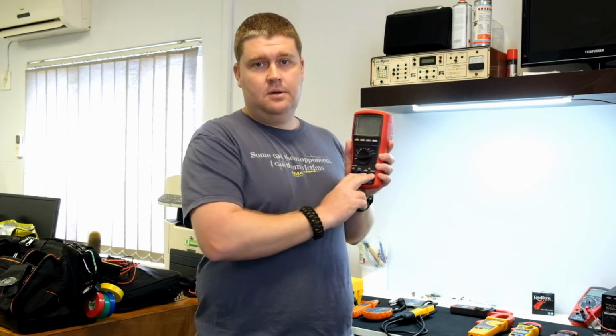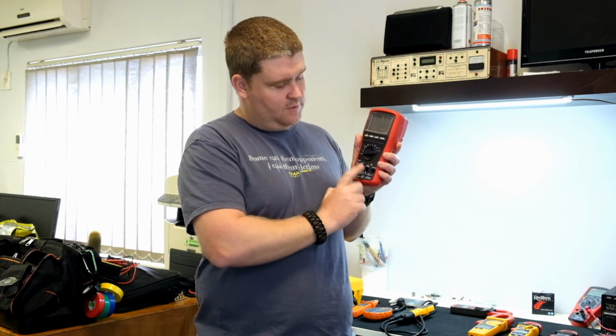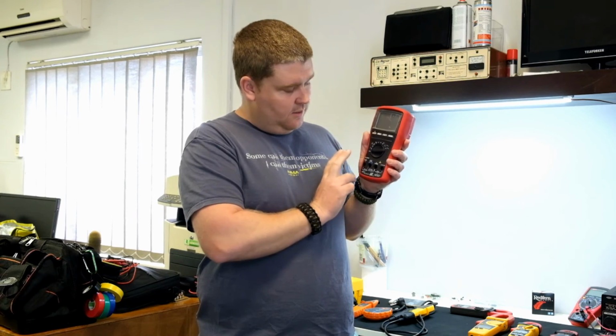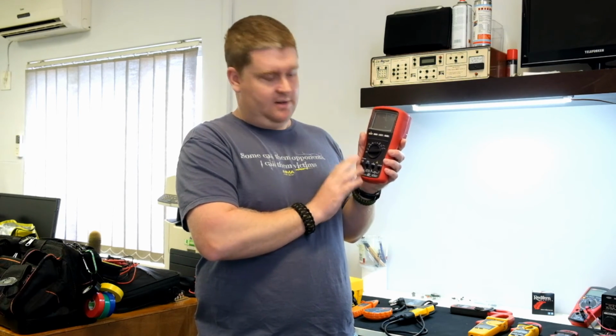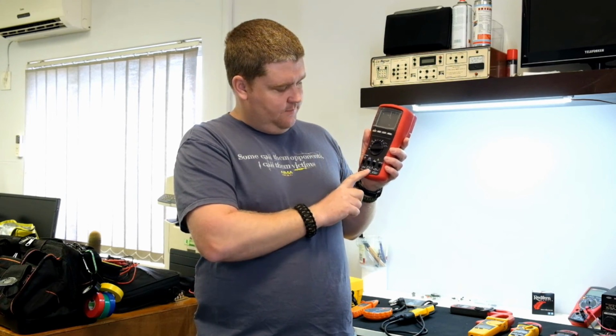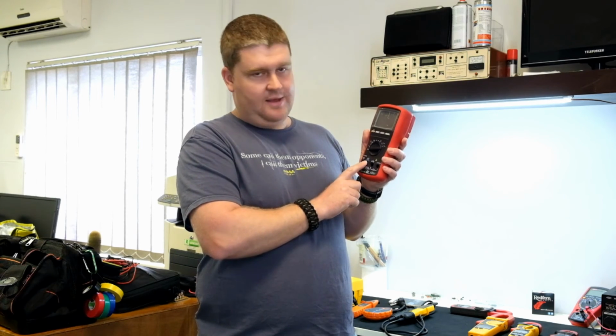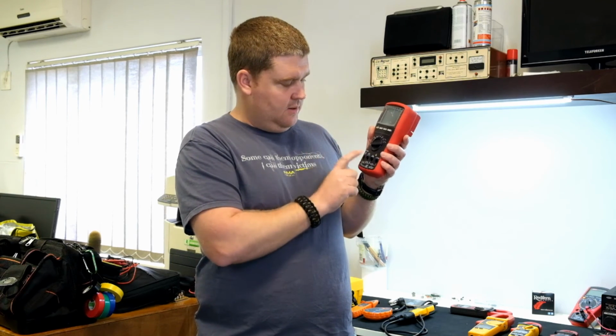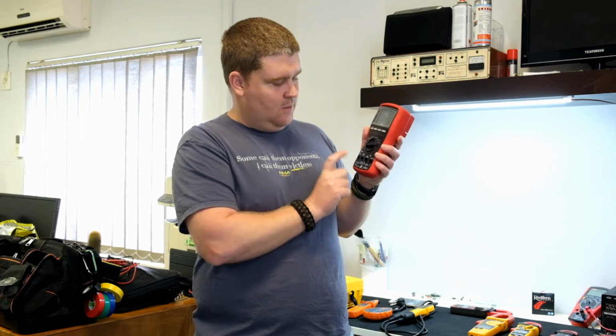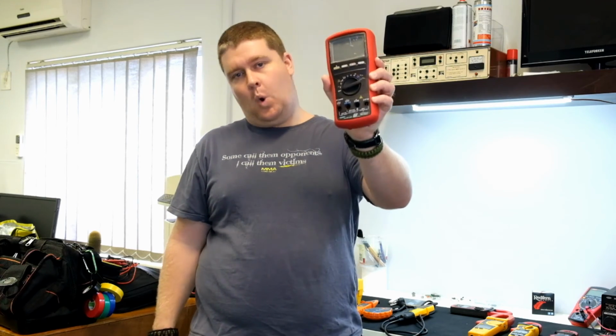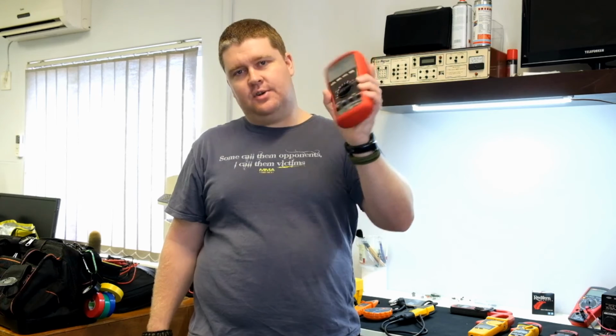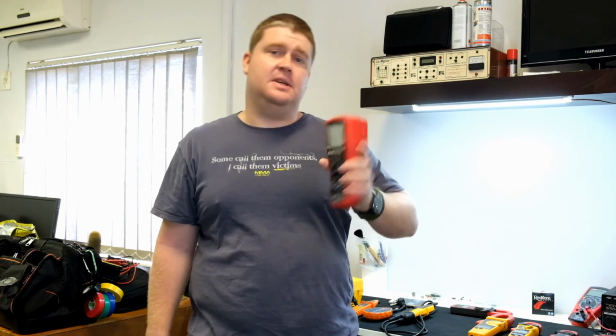On the volts - and bear in mind this is only on the volts between common and the volts connector, not the milliamps, microamps or amps connectors, since those aren't rated 1000 volts Cat 3 - the volts and common are rated 1000 volts Cat 4. That's the highest surge protection I've seen on a multimeter here in South Africa.